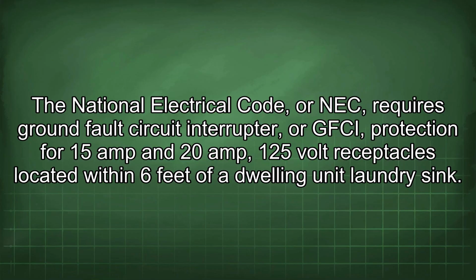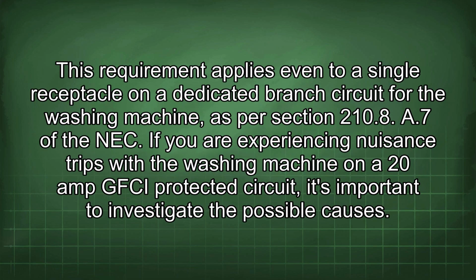The National Electrical Code, or NEC, requires ground fault circuit interrupter, or GFCI, protection for 15 amp and 20 amp 125 volt receptacles located within 6 feet of a dwelling unit laundry sink. This requirement applies even to a single receptacle on a dedicated branch circuit for the washing machine, as per section 210.8 A7 of the NEC.